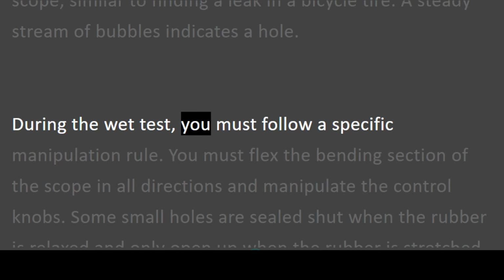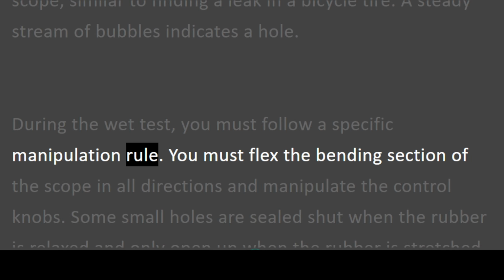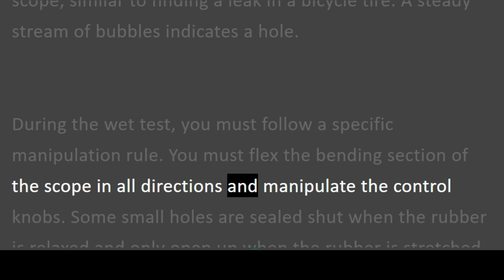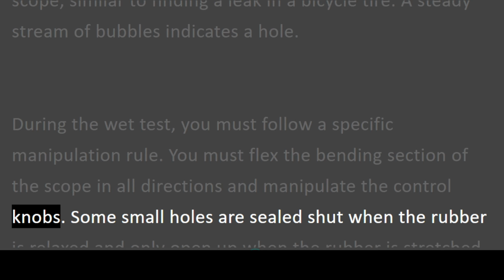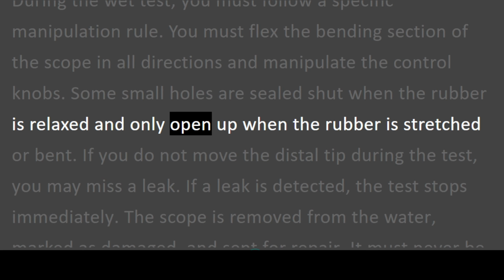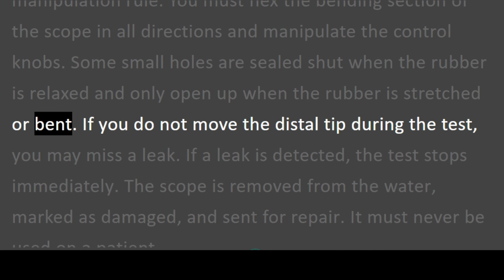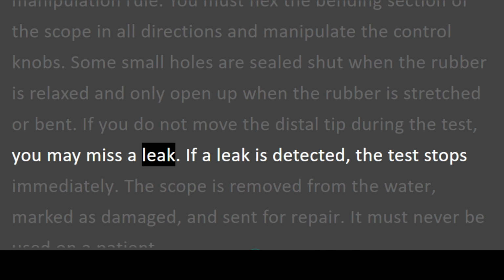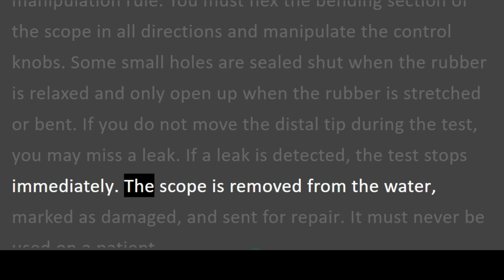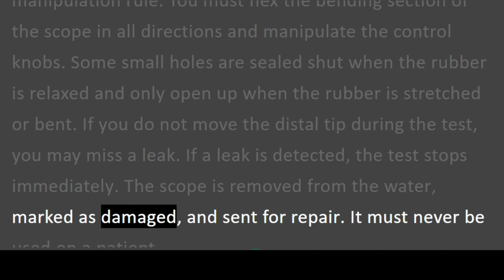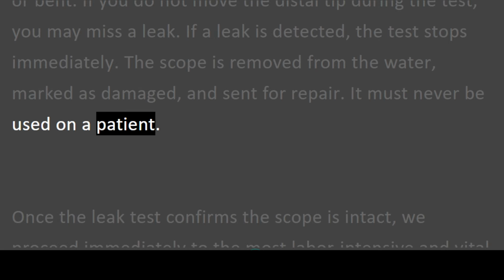During the wet test, you must follow a specific manipulation rule. You must flex the bending section of the scope in all directions and manipulate the control knobs. Some small holes are sealed shut when the rubber is relaxed and only open up when the rubber is stretched or bent. If you do not move the distal tip during the test, you may miss a leak. If a leak is detected, the test stops immediately. The scope is removed from the water, marked as damaged, and sent for repair. It must never be used on a patient.